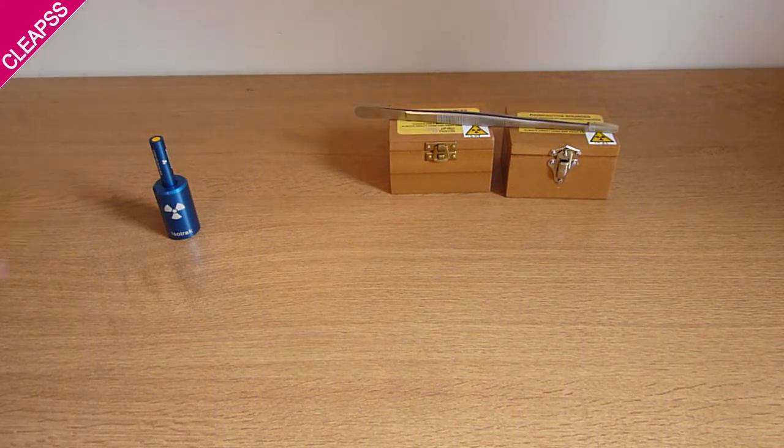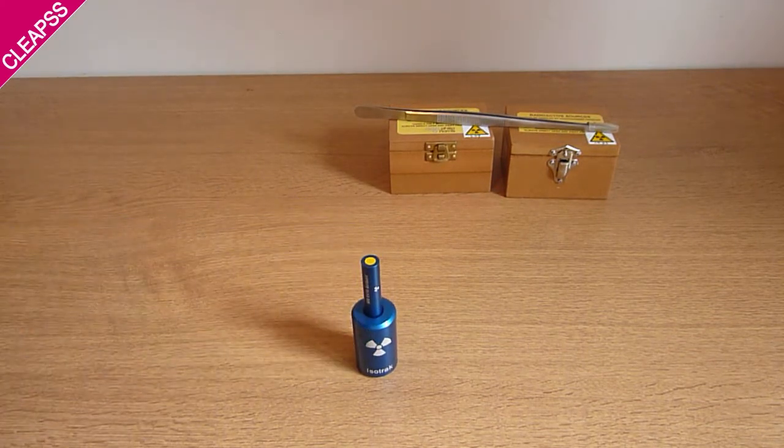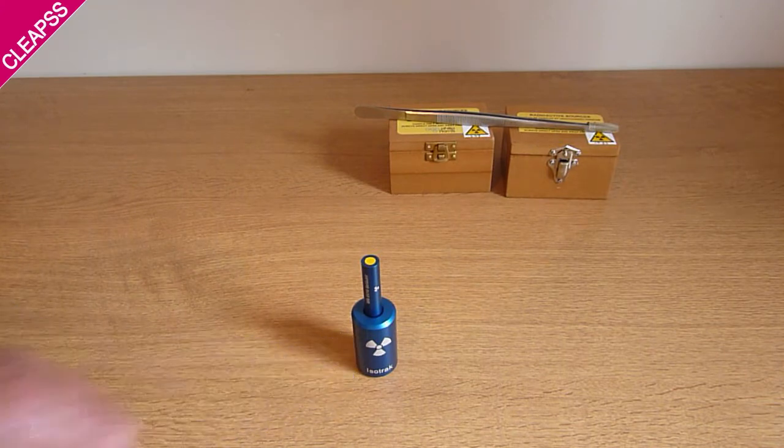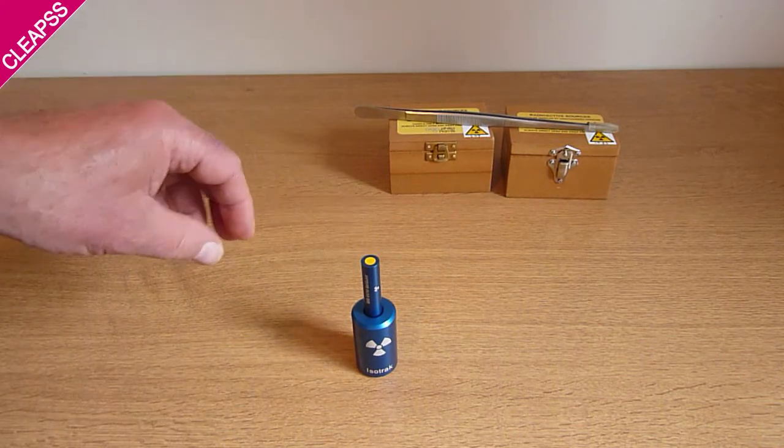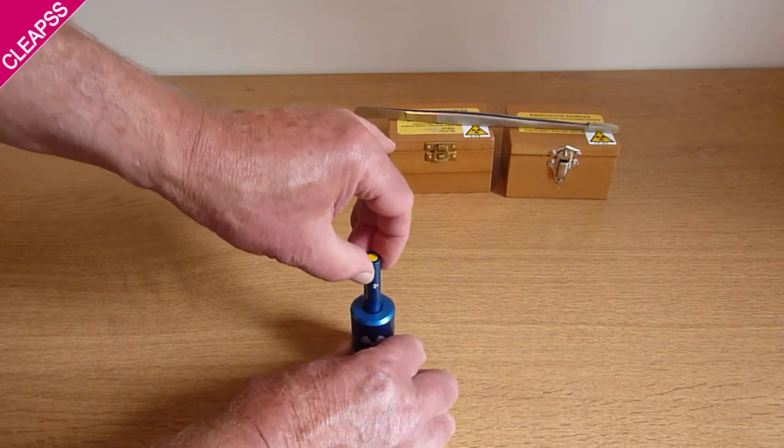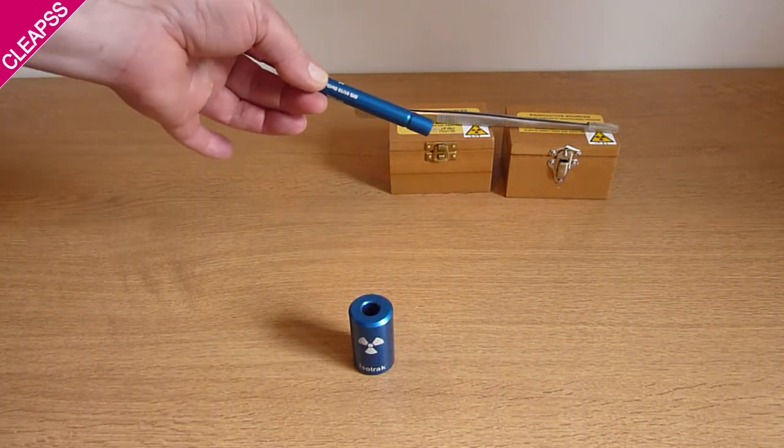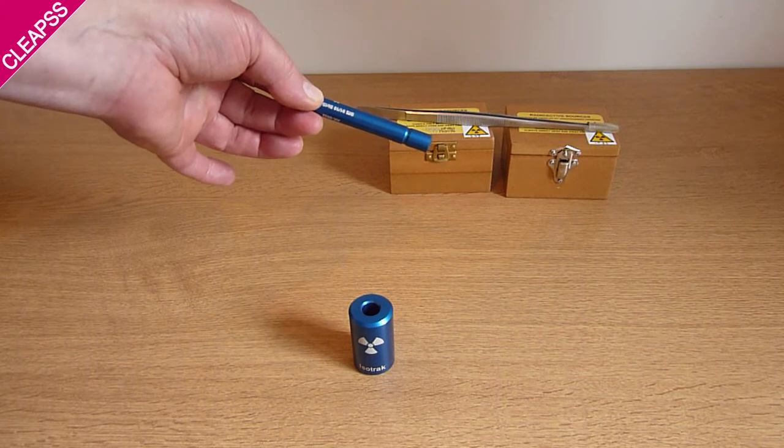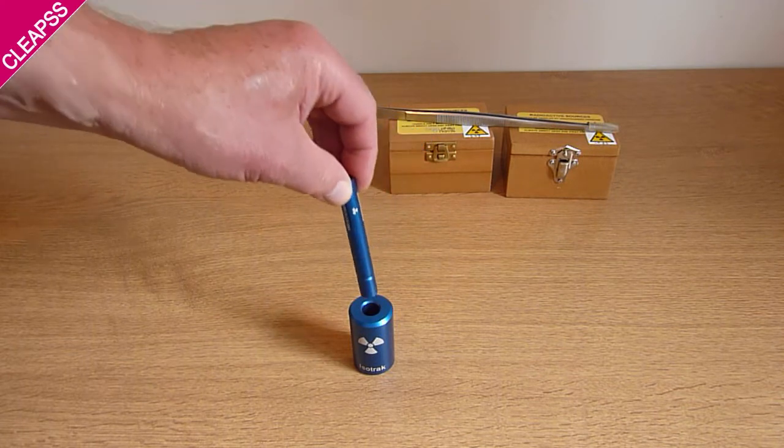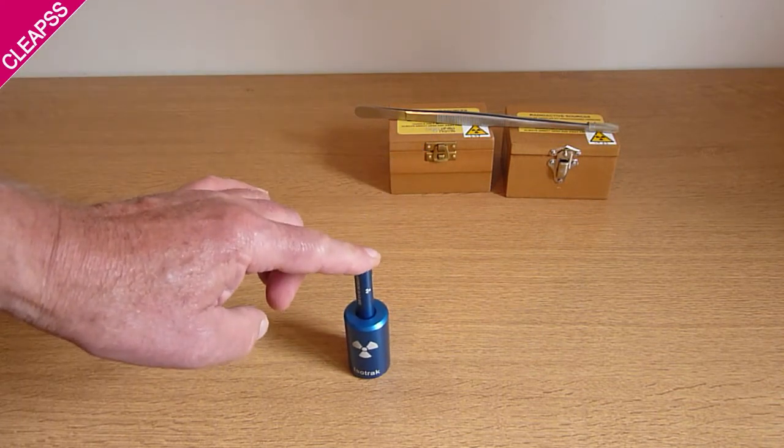Now the Isotrak source, a different design - it's an aluminium shield with a rod inside. To access the source, take it out. And this is designed to be held by hand, not with forceps. And you finish with it back into its shield, click in place.